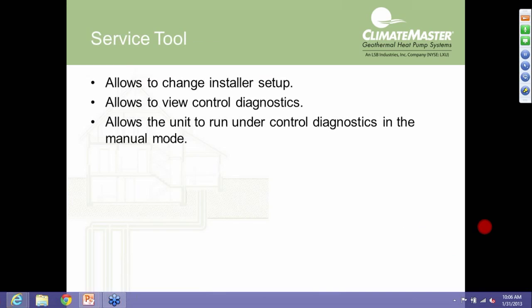Now, the service tool allows you to change any of the installer setup. It allows you to view any control diagnostics. It allows you to even run the unit in the control diagnostics in the manual mode. Again, you cannot run the unit with the service tool as the thermostat, saying, put in 70 degrees or something like that. But you can run it in manual mode, giving it specific calls. So we're going to look at some of those screenshots here coming up.